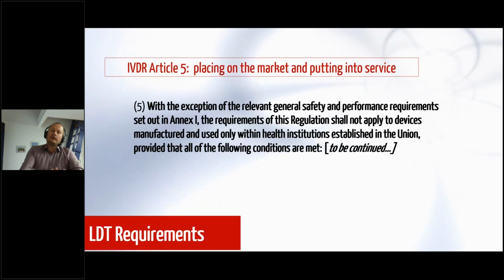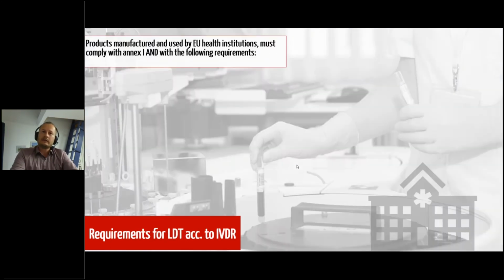And therefore we find in Article 5, placing on the market and putting into service: with the exception of the relevant general safety and performance requirements set out in Annex 1, the requirements of this regulation shall not apply to devices manufactured and used only within health institutions established in the Union, provided that the following conditions are met, which I would like to demonstrate in the next slide. So that means products manufactured and used by EU health institutions, which means medical laboratories, must comply with Annex 1 with general safety and performance requirements and need to fulfill the following requirements.